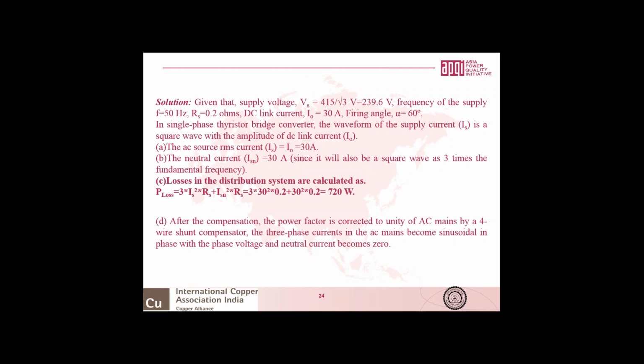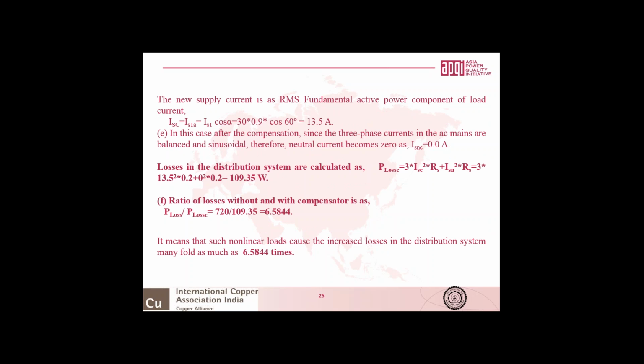After the compensation, the power factor of the AC mains is corrected to unity by a 4-wire compensator. The 3-phase currents in the AC mains become sinusoidal and in phase with the phase voltage, and the neutral current becomes 0. The new supply current after the compensation is the RMS fundamental active component of the load current. IS equal to IS1A equal to IS1 cos alpha, that is 30 into 0.9 into cos 60, that is 13.5 ampere. So this 30 ampere reduces to 13.5 ampere. And after the compensation, since the 3-phase currents in the AC mains are balanced and sinusoidal, the neutral current ISNC becomes 0.